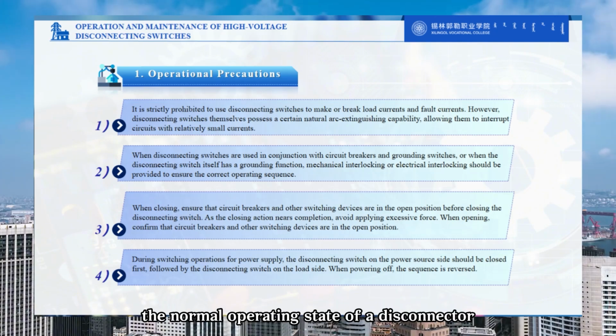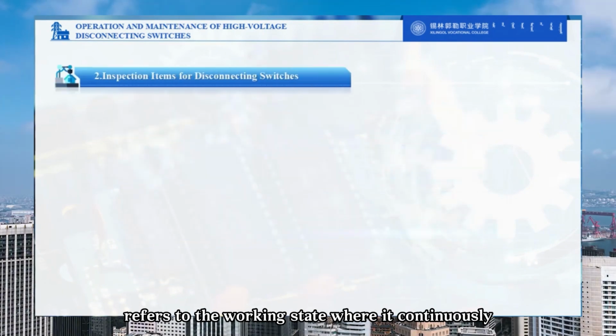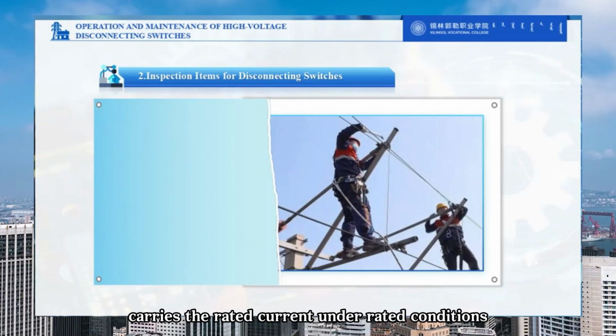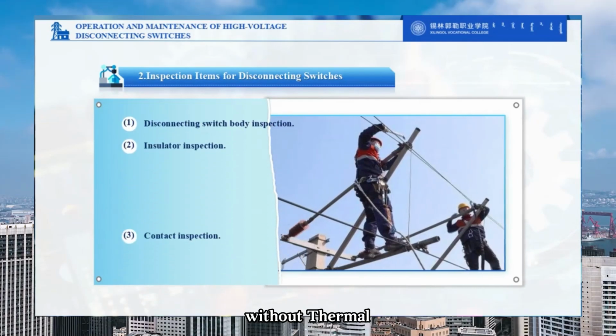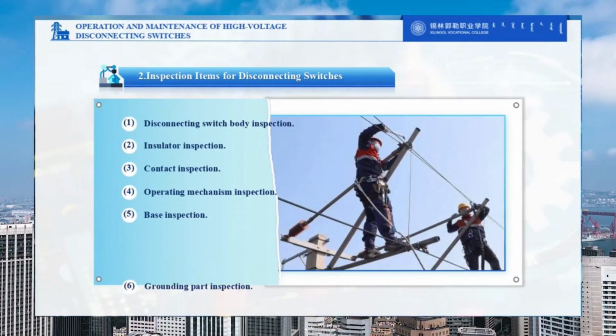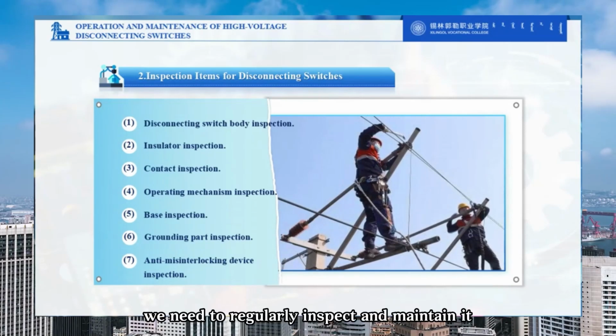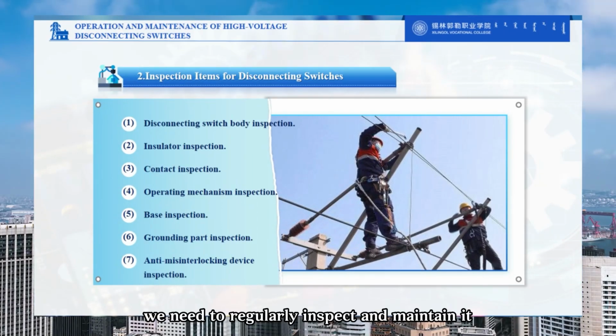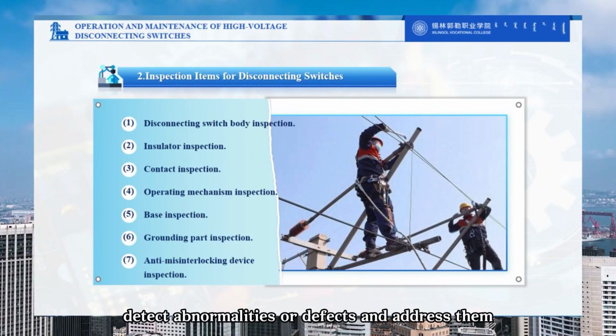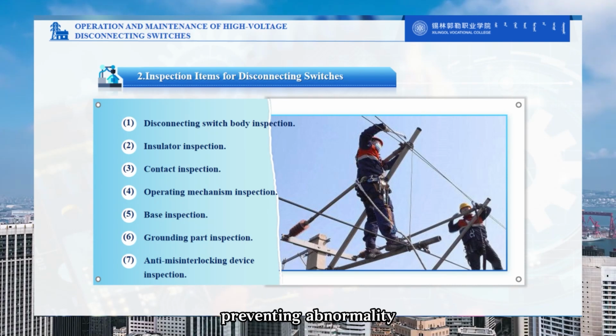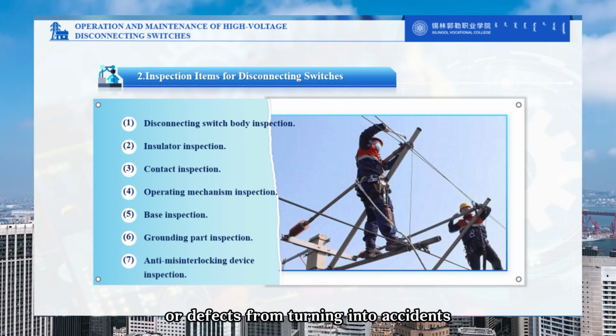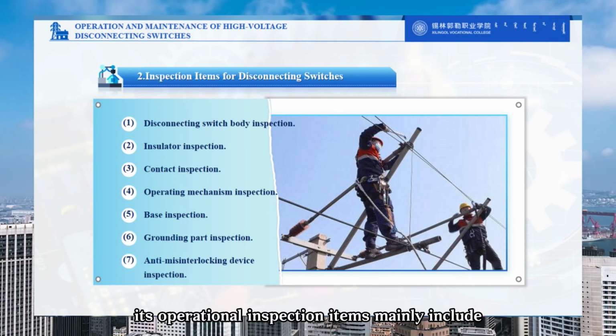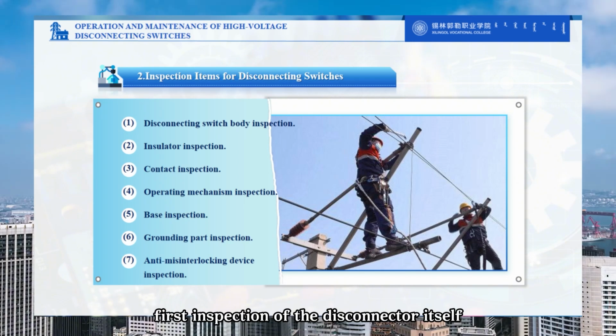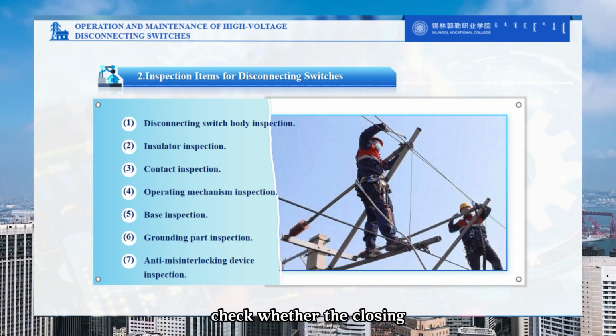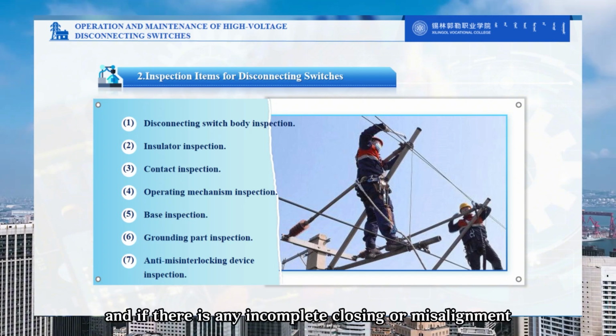The normal operating state of a disconnector refers to the working state where it continuously carries the rated current under rated conditions without thermal or dynamic stability failure. To maintain its normal working state, we need to regularly inspect and maintain it, promptly detect abnormalities or defects and address them, preventing abnormalities or defects from turning into accidents. Its operational inspection items mainly include: first, inspection of the disconnector itself. Check whether the closing condition of the disconnector is good, and if there is any incomplete closing or misalignment.